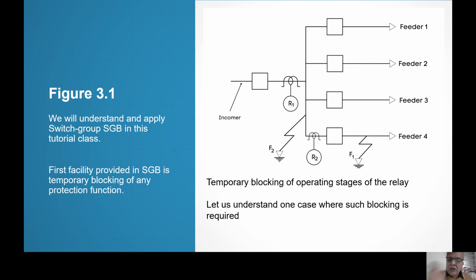So once the relay R2 senses the fault, it gives a signal to relay R1. And you see, this signaling facility also need not be using wires. Nowadays, they are using Ethernet cables, and other kinds of cables also. Using those cables, you can have communication between R2 and R1. R2 will say to R1 that I have sensed the fault. So you need not worry. I'm going to take care of it. So you need not give backup now. So R1 will be blocked.